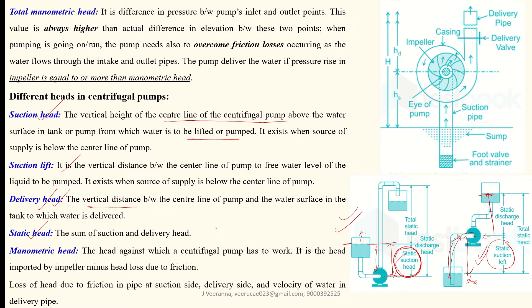Static head is the sum of both the suction head and the delivery head. Manometric head is the most important — it is the head against which the centrifugal pump must work to overcome friction losses so the water can be pumped to the target location. The total manometric head is the difference between the pressure at the inlet and pressure at the outlet, and it is always higher than the actual elevation difference because it must overcome friction losses.